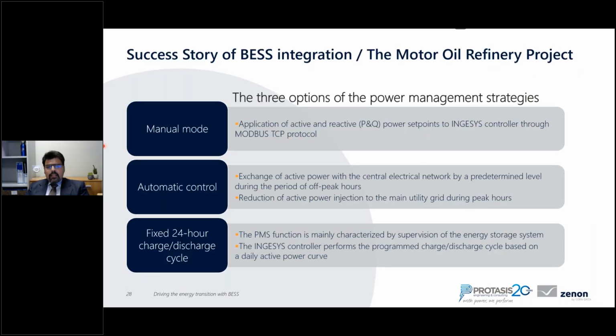In this section, we're presenting the main operating modes. The system has actually 3 main operating modes. The manual mode, in which the SCADA system issues active and reactive power set points to the battery controller. The automatic control mode, where the exchange of active power between the refinery and the grid is predetermined, ensuring the reduction of active power injection to the grid. The fixed mode, where the system follows a predefined time schedule of charging and discharging cycles based on the refinery energy needs.